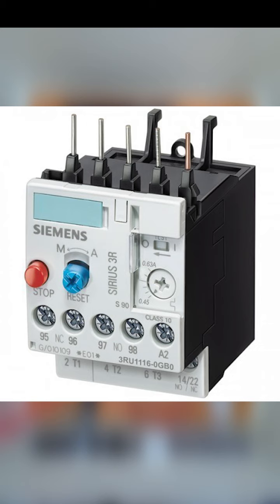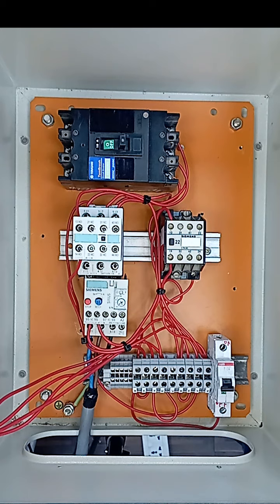Overload protection for an electric motor is necessary to prevent burnout and to ensure maximum operating life. Under any condition of overload, a motor draws excessive current that causes overheating. Since motor winding insulation degrades due to overheating, there are established limits on motor operating temperatures to protect the motor from overheating. Overload relays are employed on a motor control to limit the amount of current drawn. Please note that the overload relay does not provide short circuit protection. That is the function of overcurrent protective equipment like fuses and circuit breakers.